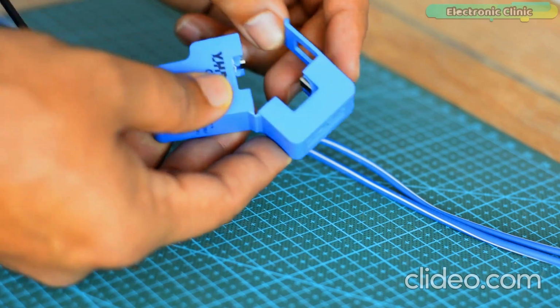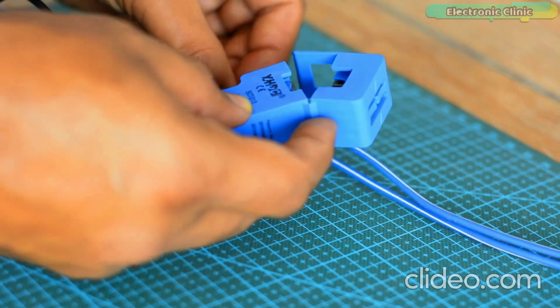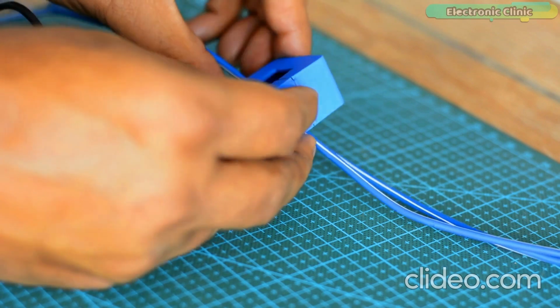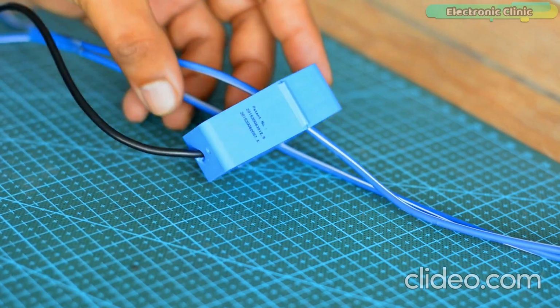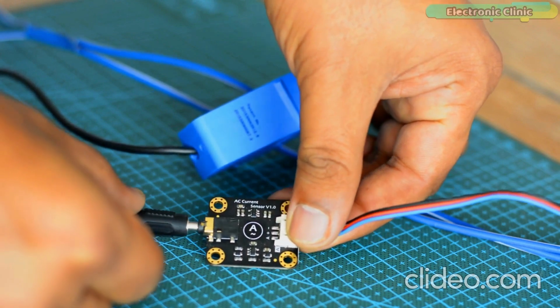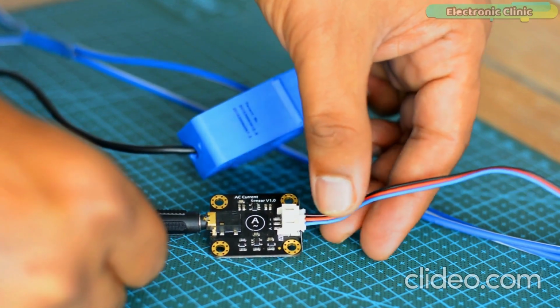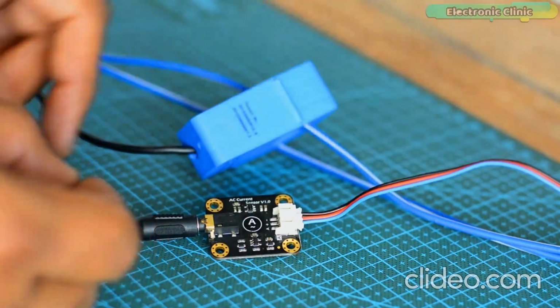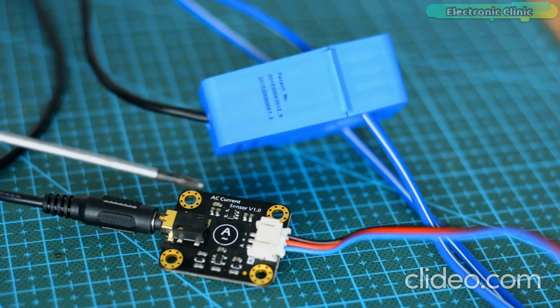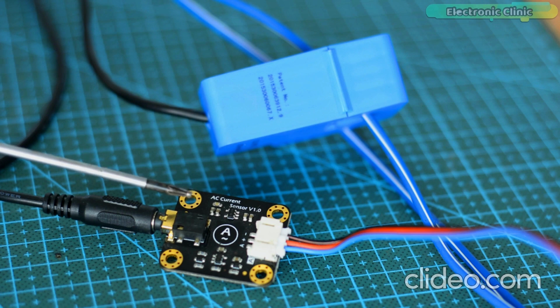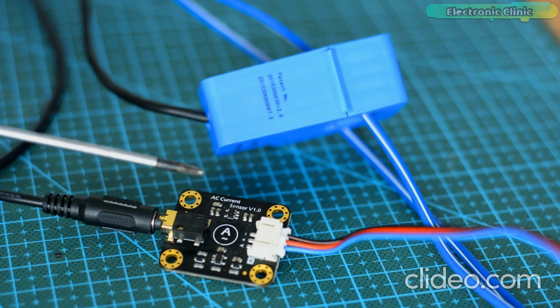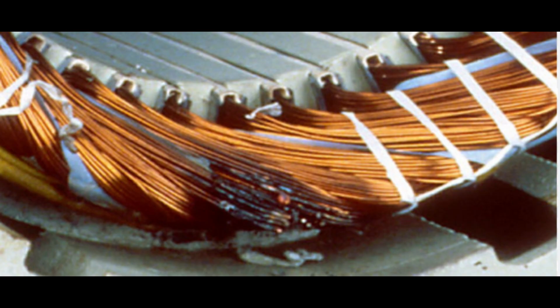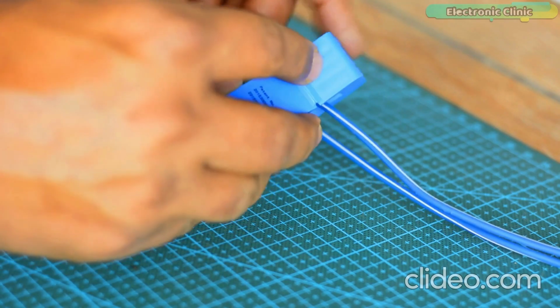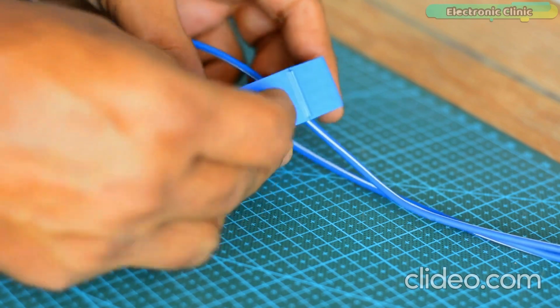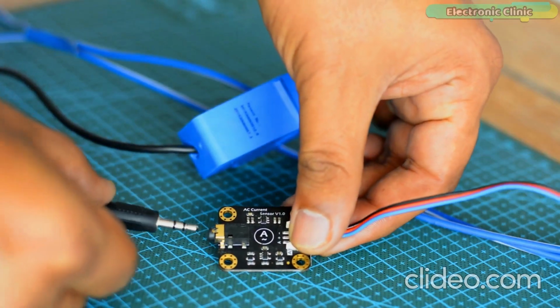When current flows through the live wire, it creates a magnetic field around the wire. The current transformer, when clamped around the live wire, detects this magnetic field. The current transformer has a core that can be opened and closed, allowing it to be installed without disconnecting the wire. Leakage current occurs when there is an unintended path for current to flow, typically due to insulation failure or damage. In a properly functioning circuit, the current in the live wire should equal the current in the neutral wire. If there is a difference, it indicates leakage.